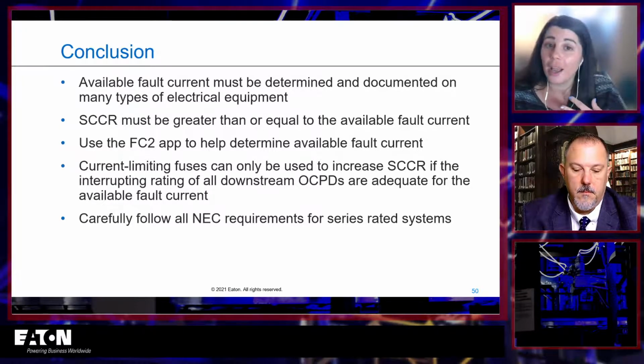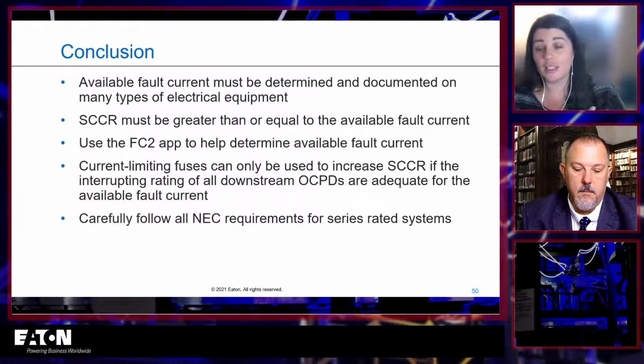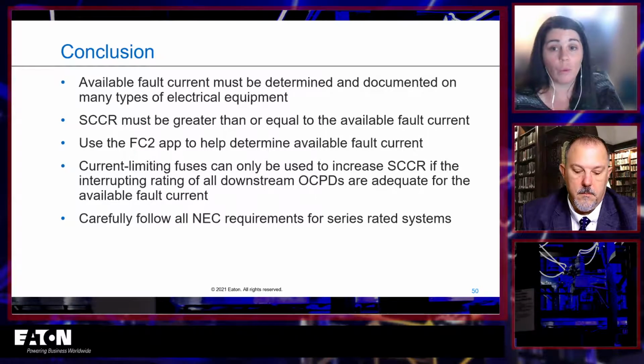You can use the FC Squared app to help you determine what that available fault current is. It's a great thing to download and use. Current limiting fuses, you can use it to increase SCCR only if the interrupting rating of the downstream device is adequate. You could use a series rating if it's not, but make sure you carefully follow all of the NEC requirements when it comes to series ratings. And we always, always, always recommend a fully rated system over a series rated system.